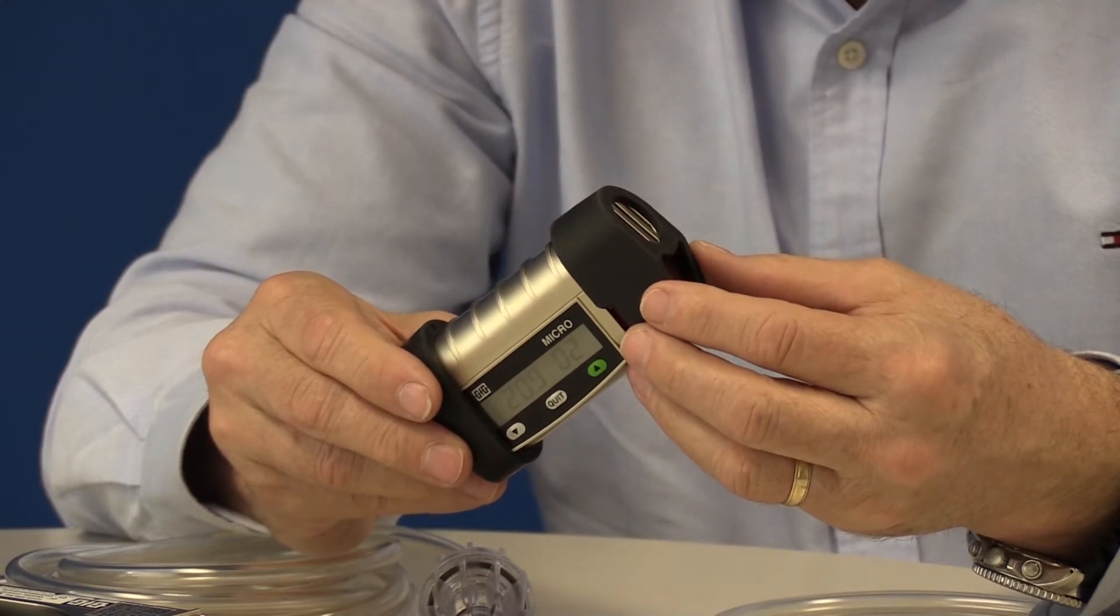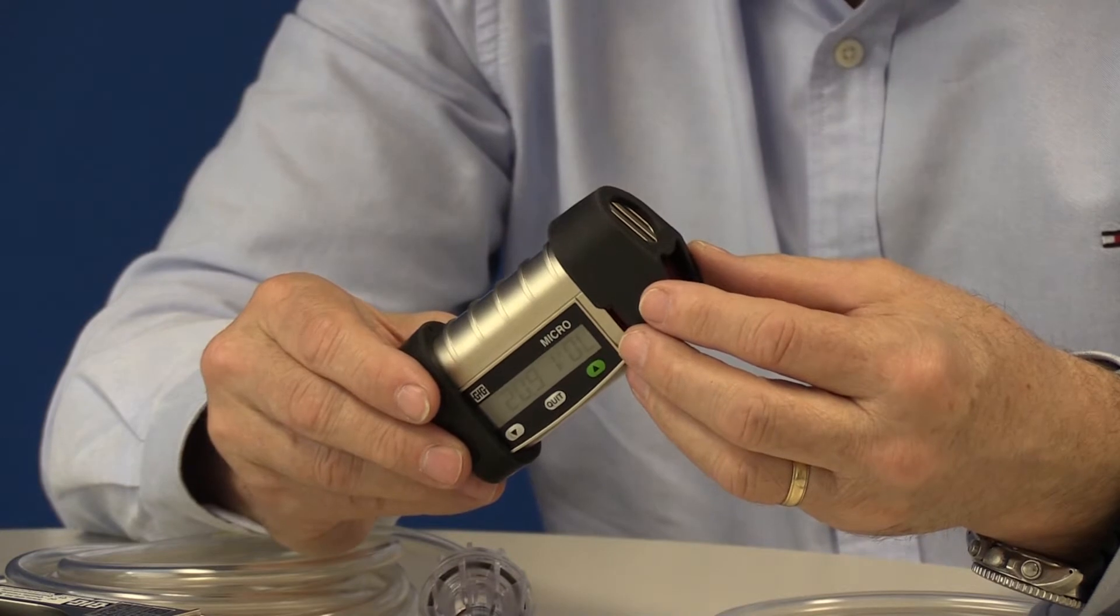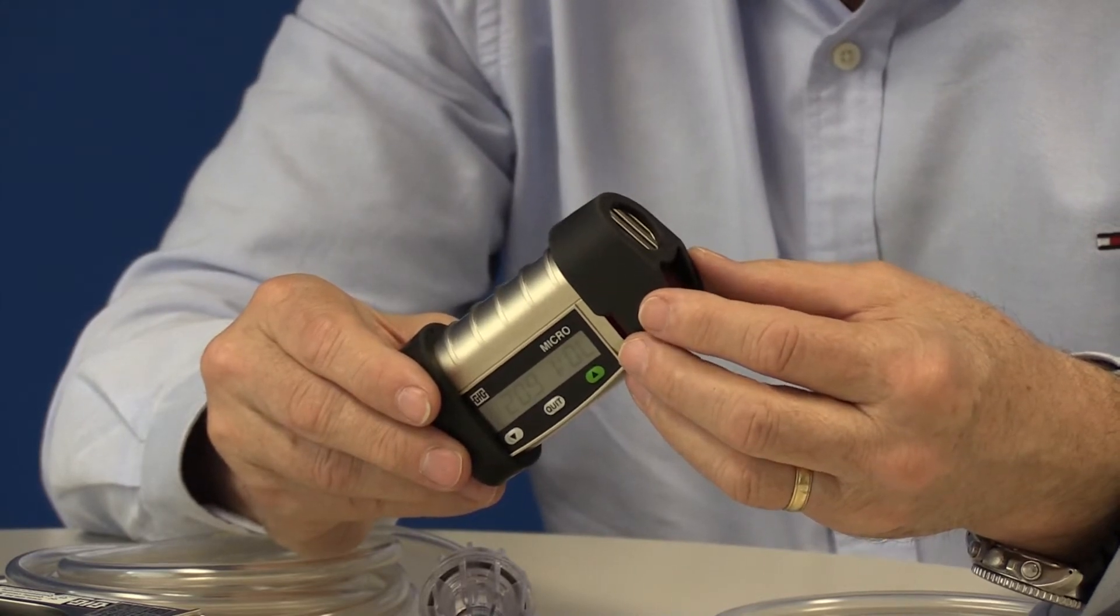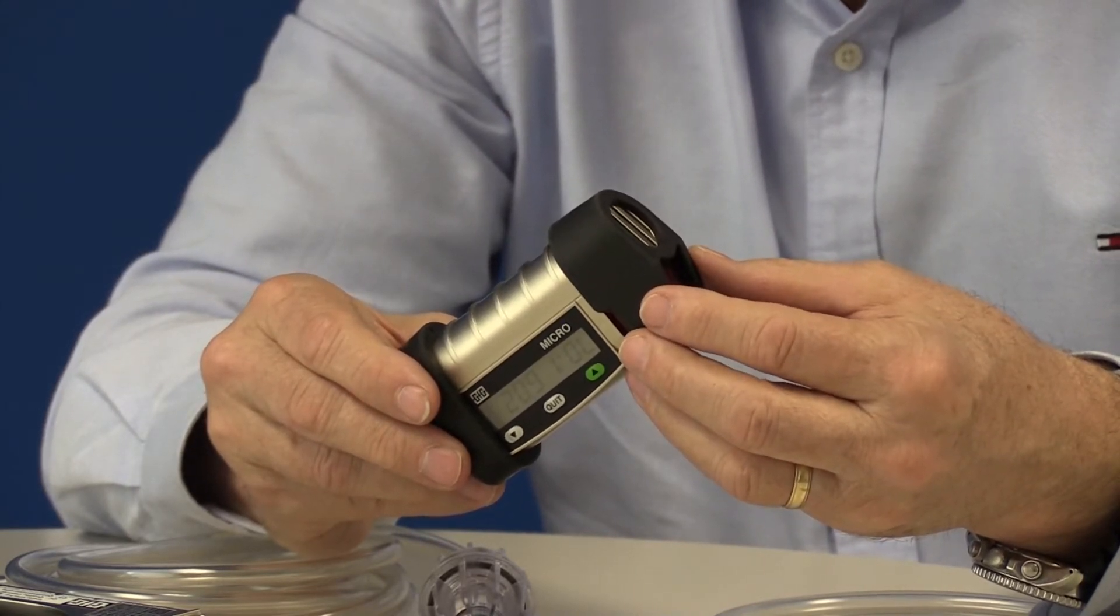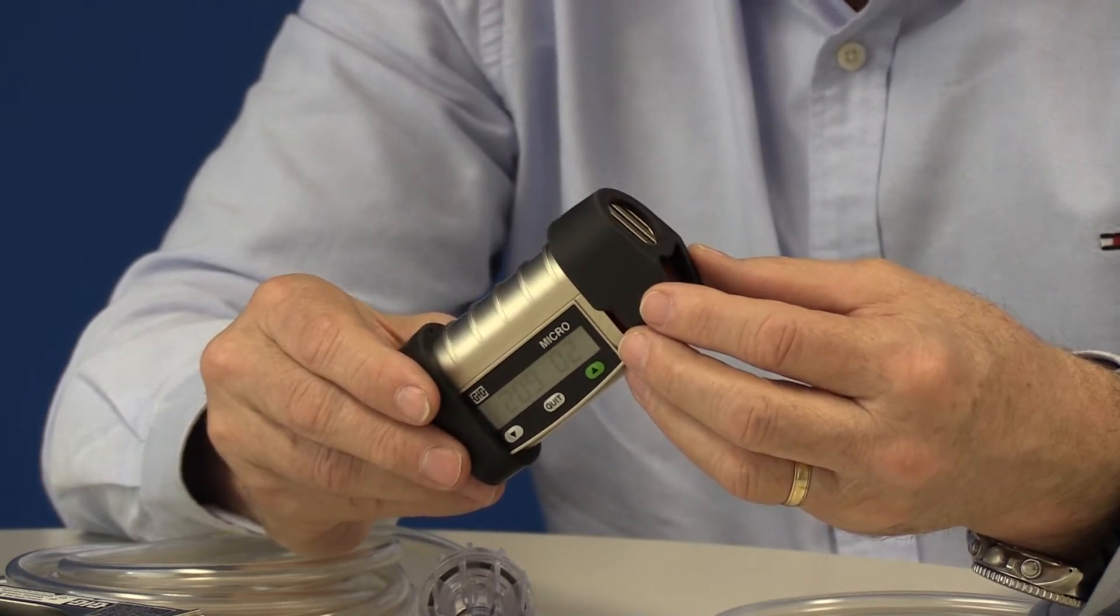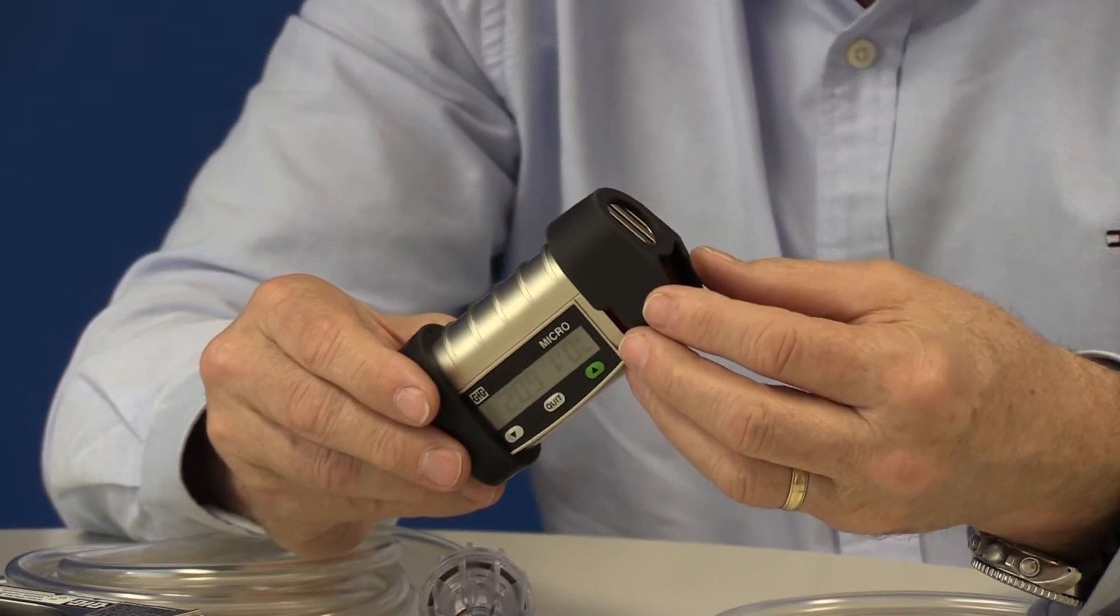Many ranges, many gases. It's a very flexible product. Most of the time the Micro Four is going to be used in simple diffusion operation. What that means is you depend on the currents in the air that immediately surrounds the instrument to help the molecules that are present to diffuse into the sensor where the gas is measured.